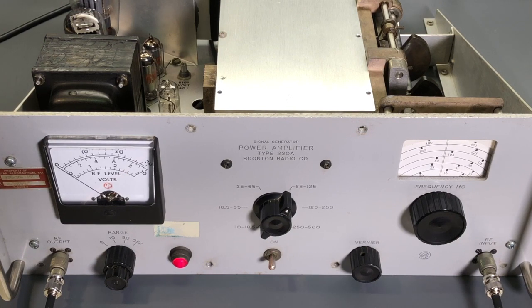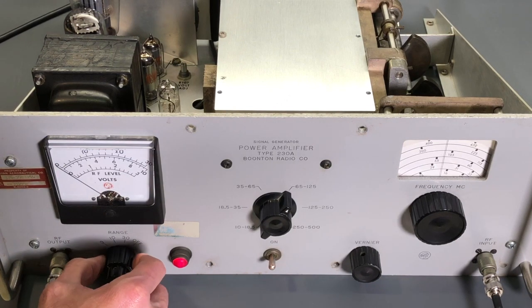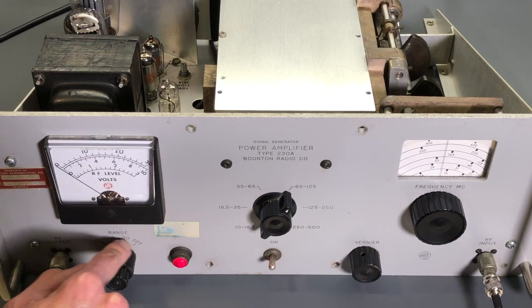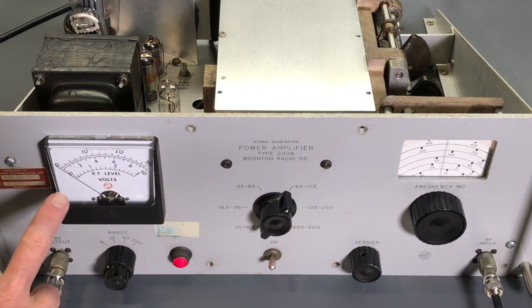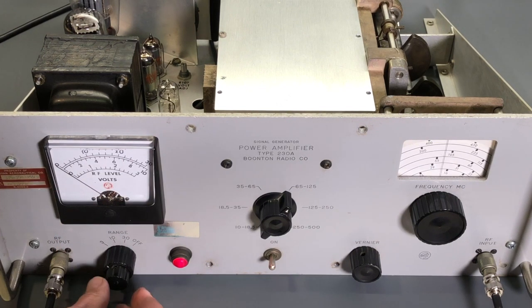Now there's an adjustment, you can't see it on the camera, but down in the chassis over here, it's R113, it's diode compensation. And the purpose of that is so that when you change the range from 3, 10, and 30 right here on this selector switch, that the meter stays at 0. Now as you recall, this adjustment is an electrical 0. You can see how the meter moves while I'm turning that adjustment.